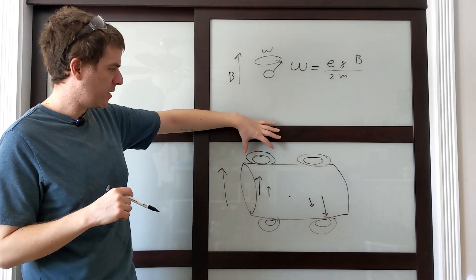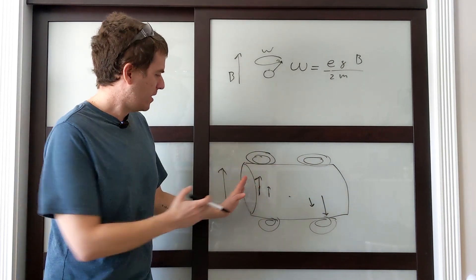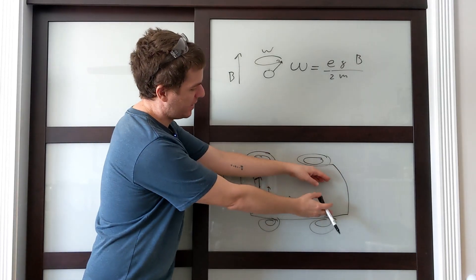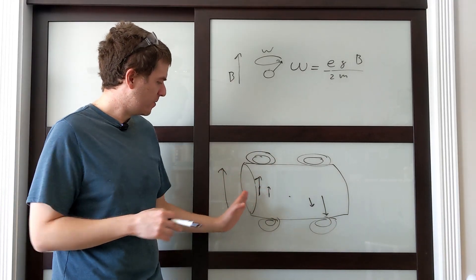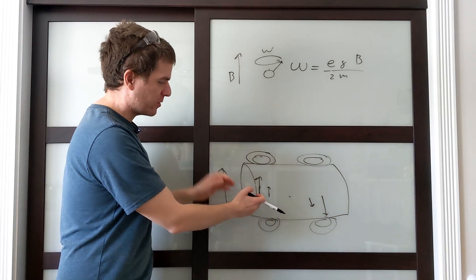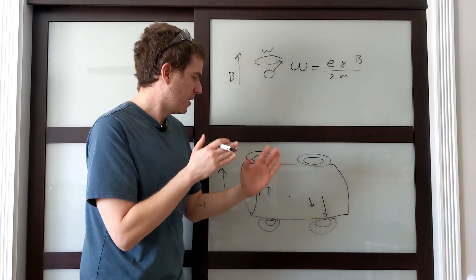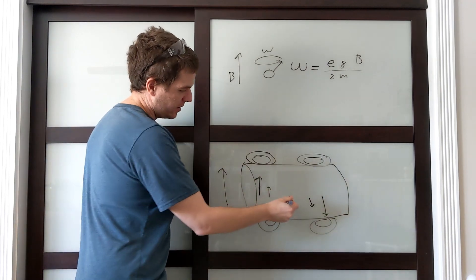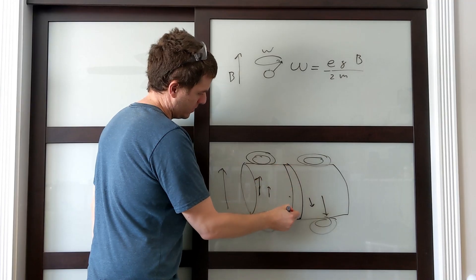What we can do is create magnetic coils that create a gradient. What I mean by a gradient is that on one side the magnetic field is higher, giving a little bit of push, and on the other side it's taking away a little bit. So the magnetic fields here add up and here they subtract, and the Larmor frequency is higher here and lower here. But if we're only sending in one specific frequency, that really means guys over here are not going to resonate, guys over here are not going to resonate, and only this thin slice here is going to resonate.